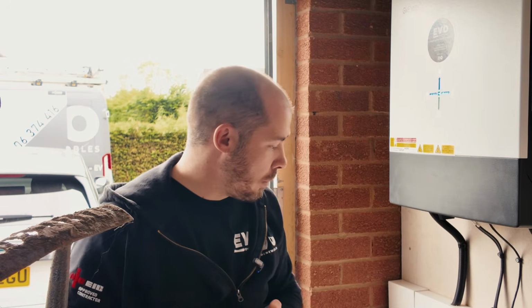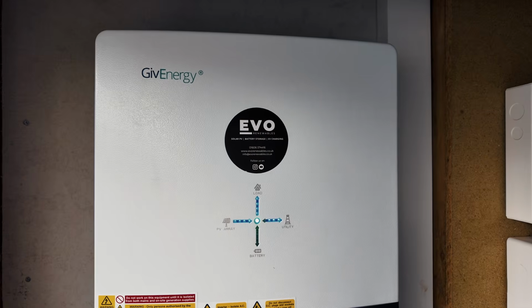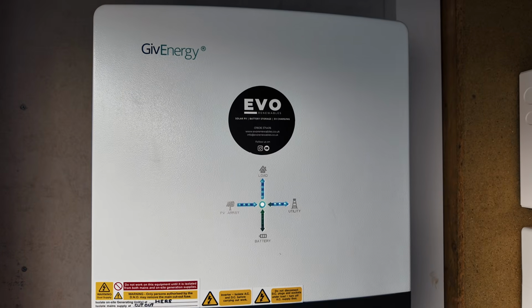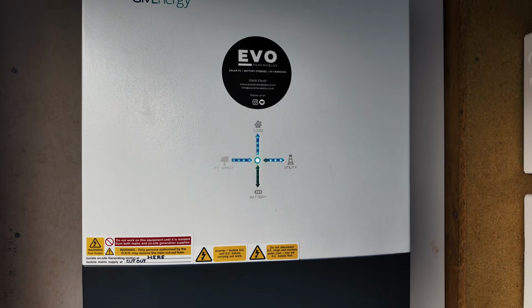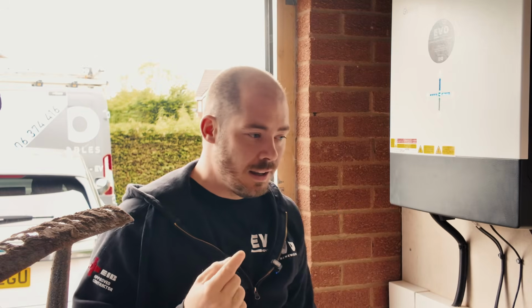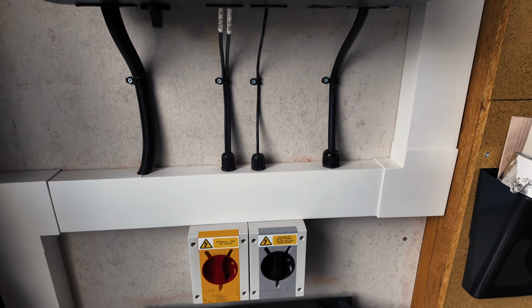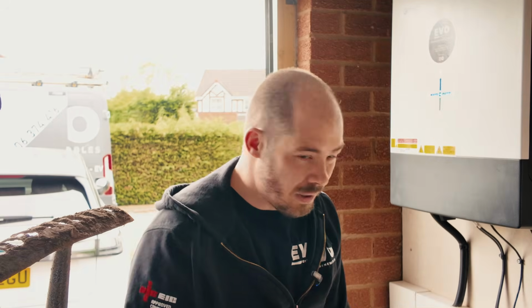A couple of things I'm going to check. Modbus and CT clamp, because without those the batteries won't be charging or discharging, regardless of whether it's from solar or grid charge. So I need to check the CT and the Modbus. Also going to check the battery voltage to make sure it's good. If it's not, we can charge that, and check the MCB. I have had it before where the MCB is reading voltage on the bottom terminals but not on the top, and we can swap it over.